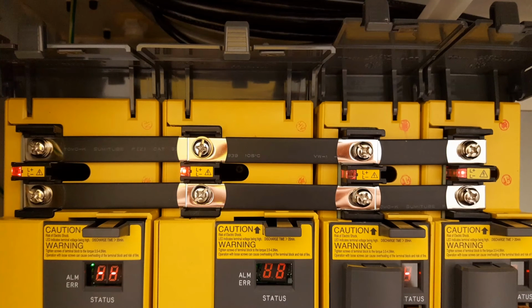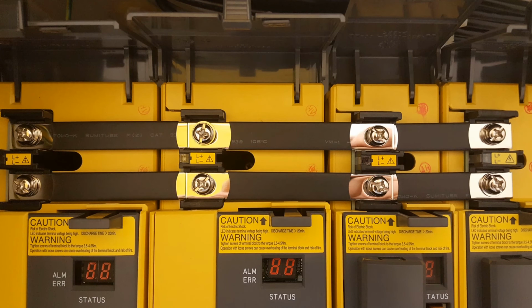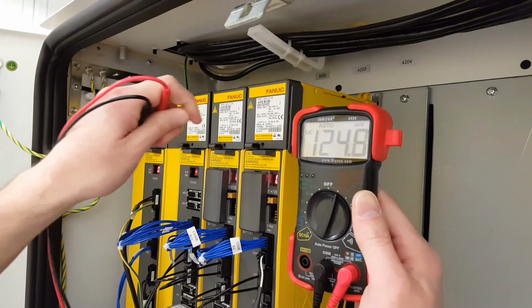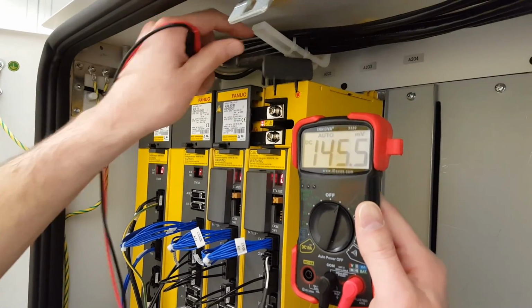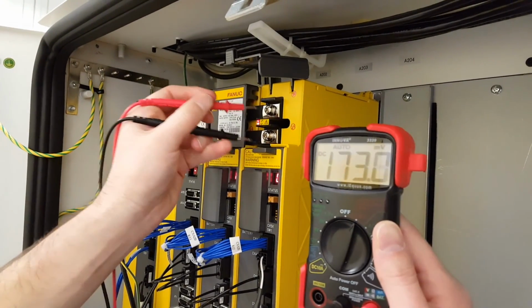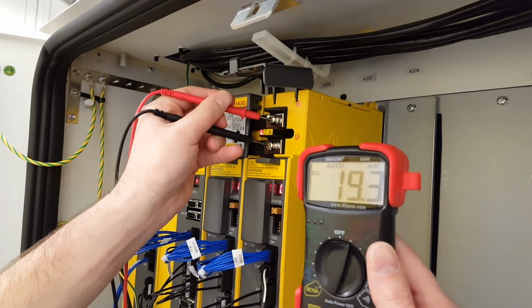The DC link is located along the top of the drive units. Flipping up the doors will reveal two sets of very substantial bus bars. The top is positive, the bottom is negative. In between the bus bars are LEDs that indicate whether the bus is charged up or not. In this example, the bus is charged. And in this one, it's not. Using the screws as measurement points, check for DC between the two bars.